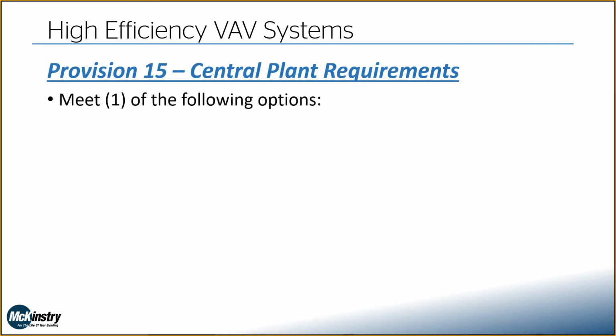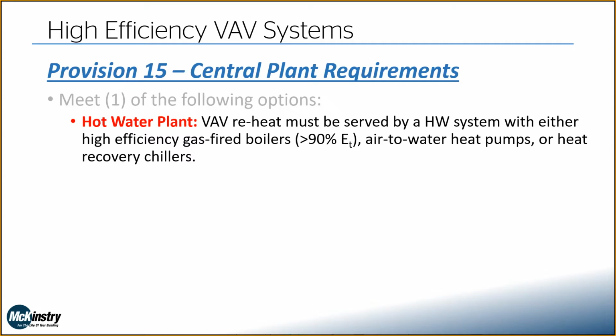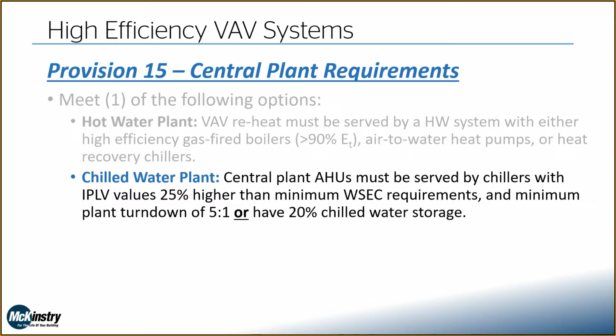Central plant requirements. So typically in a VAV system, we will have a central plant. And for high efficiency VAV, we need to meet one of the following two options. So the first option, in our hot water plant, we have to have a hot water system served by either high efficiency gas-fired boilers, air-to-water heat pumps, or heat recovery chillers. Probably the most common application we would see is high efficiency boilers. We see condensing boilers all the time, but the point is they want that hot water plant to be efficient. So we need to either meet that, or on our chilled water plant, our central plant has to be served with chillers with IPLV values 25% higher than what's required by code, and have a 5-to-1 turn down or 20% chilled water storage. So we only need to meet one of these two.